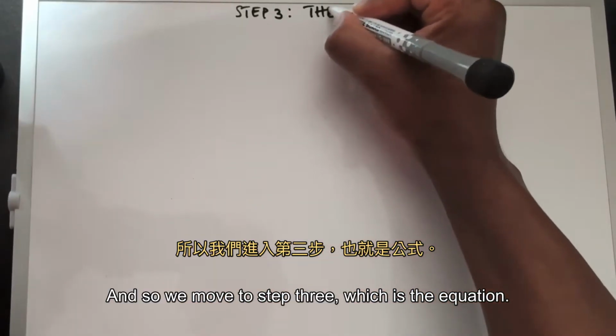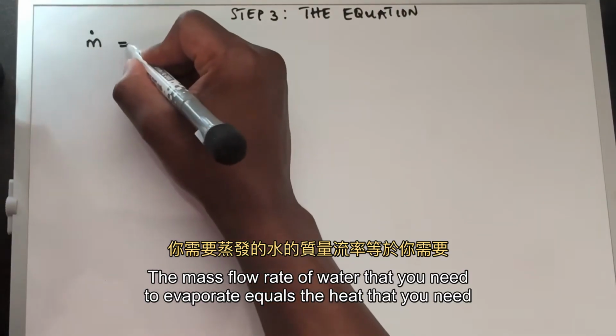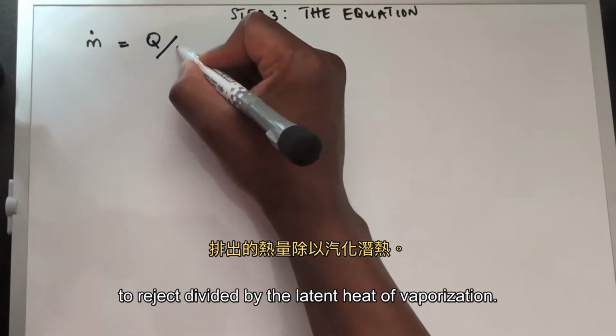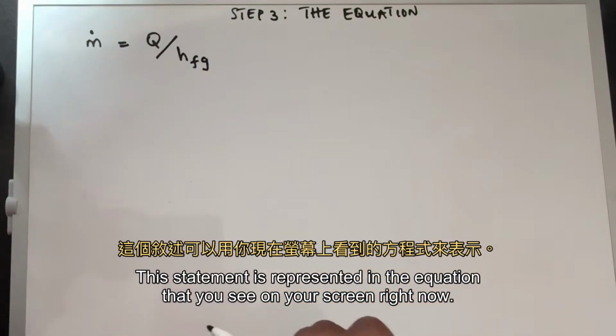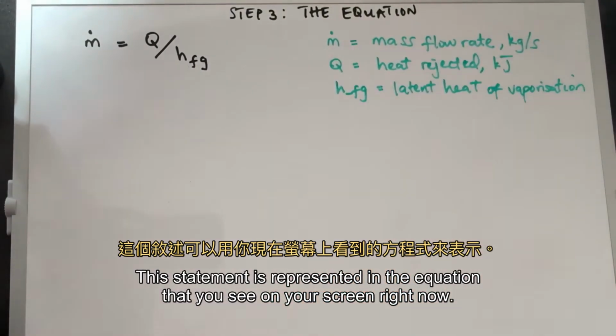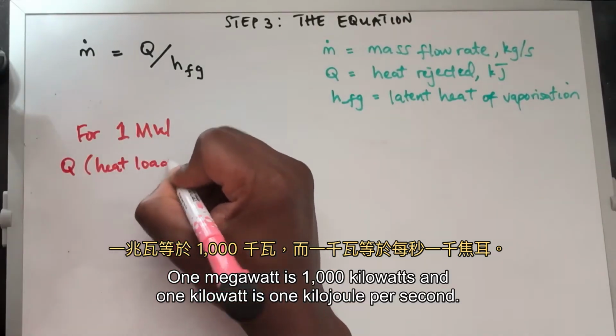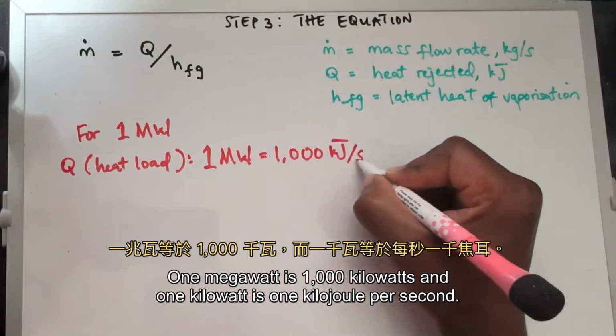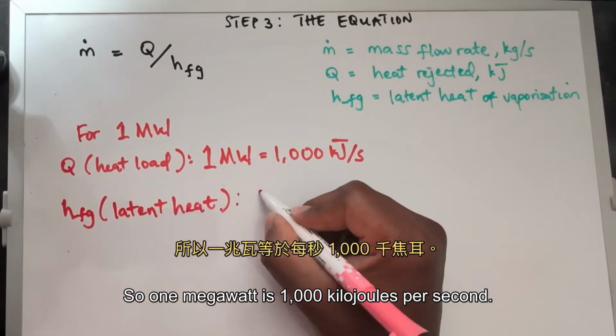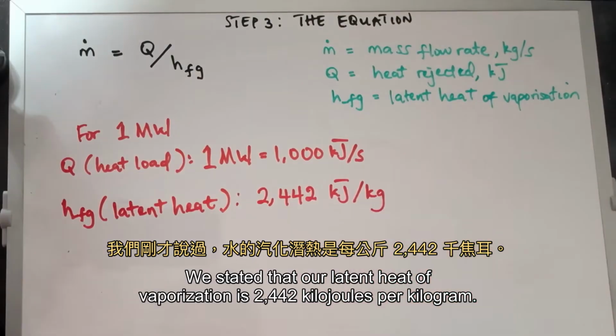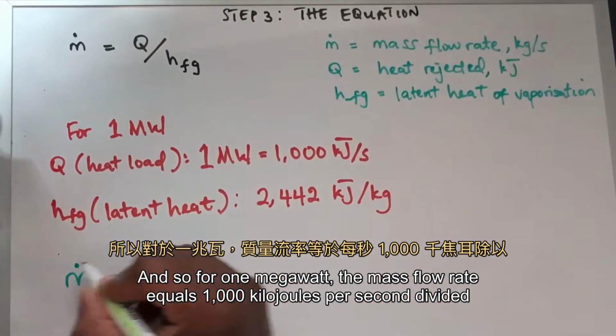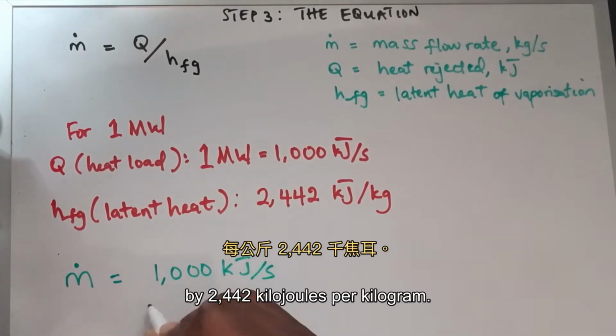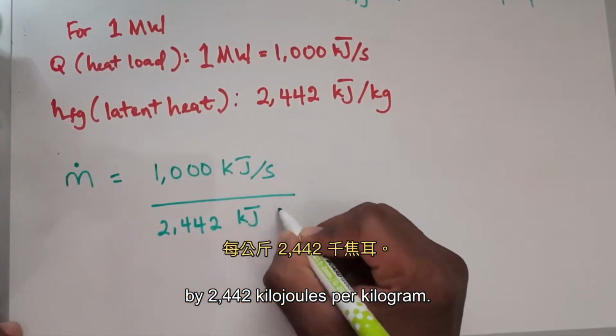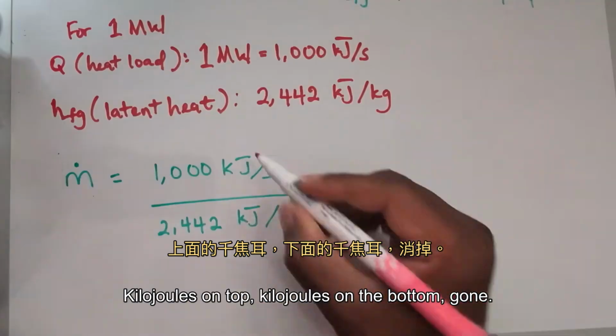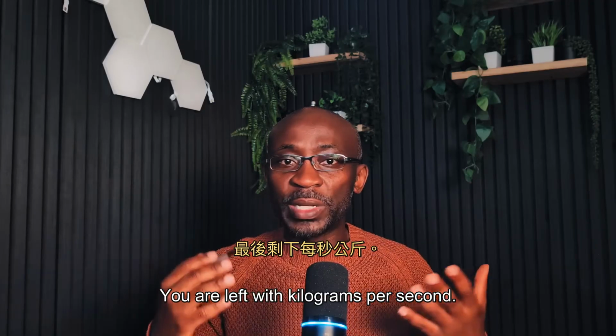And so we move to step three, which is the equation. The mass flow rate of water that you need to evaporate equals the heat that you need to reject divided by the latent heat of vaporization. This statement is represented in the equation that you see on your screen right now. 1 megawatt is 1,000 kilowatts, and 1 kilowatt is 1 kilojoule per second. So 1 megawatt is 1,000 kilojoules per second. We stated that our latent heat of vaporization is 2,442 kilojoules per kilogram. And so for 1 megawatt, the mass flow rate equals 1,000 kilojoules per second divided by 2,442 kilojoules per kilogram. Watch the units cancel. Kilojoules on top, kilojoules on the bottom, gone. You are left with kilograms per second.